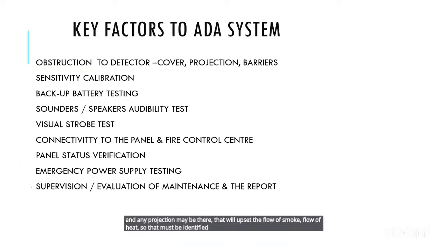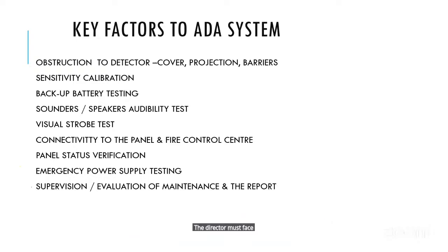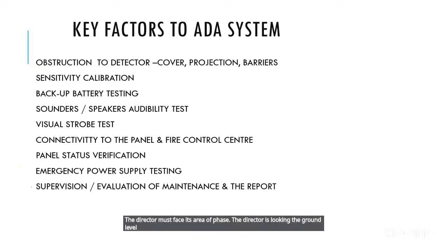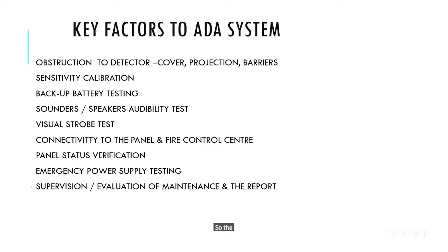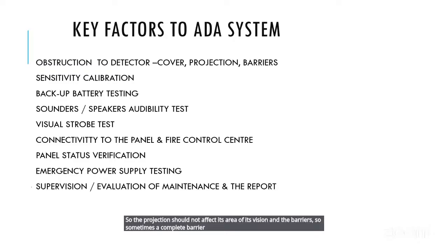The detector must face its area of coverage. The detector is looking at the ground level, 9 square meters or 8 square meters, like that. The detector should face the ground level correctly, so that wherever the smoke or heat is produced, it will reach the detector. So the projection should not affect its area of vision. And barriers: sometimes a complete barrier will be there. The detector is isolated from its risk factor. That is a barrier.